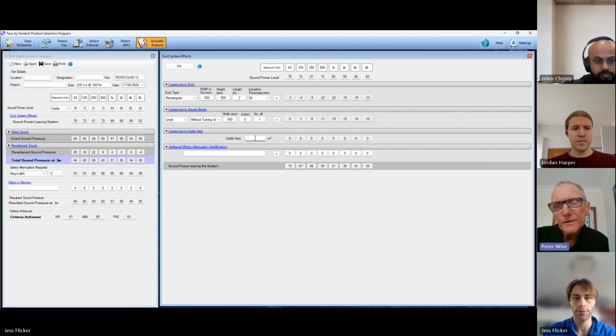So if you've got say a 600 by 600 diffuser in the ceiling, the neck size might be somewhere between 300 square and 450 square or something. So whatever that neck size is, you put that in there - just so it's a 300 square neck, which is 0.1 of a square meter.